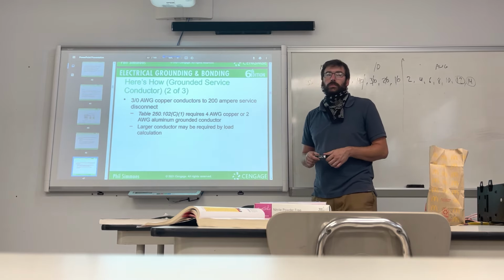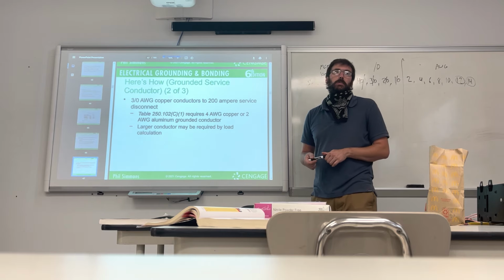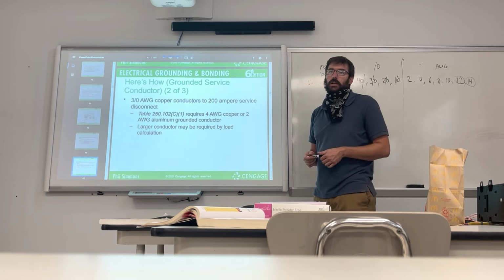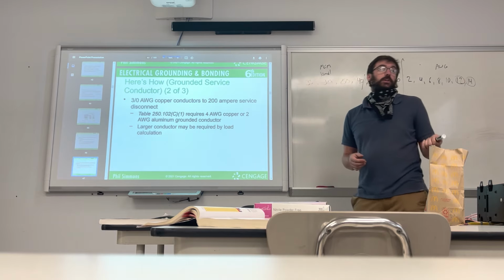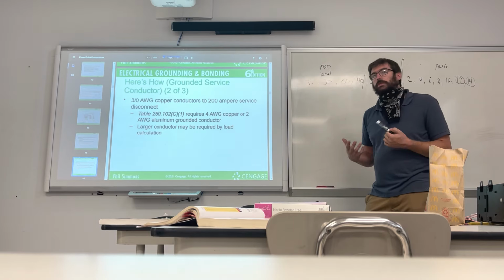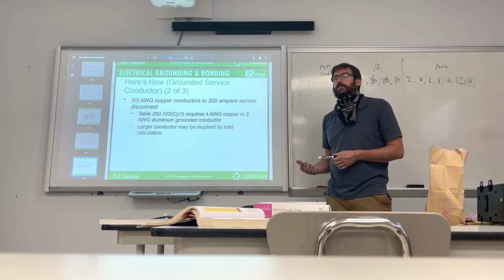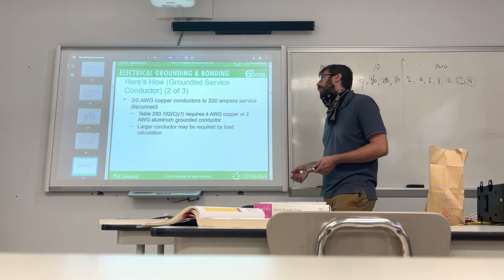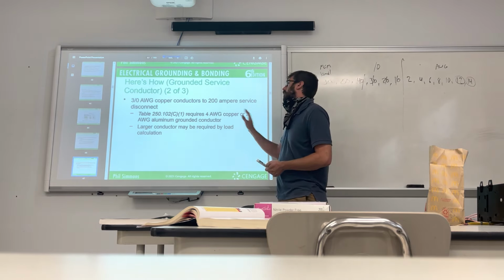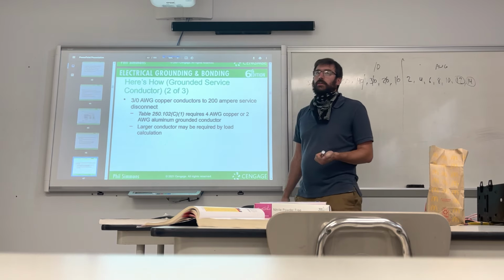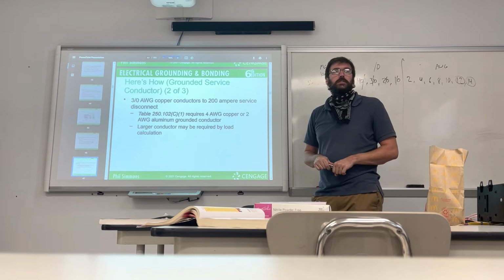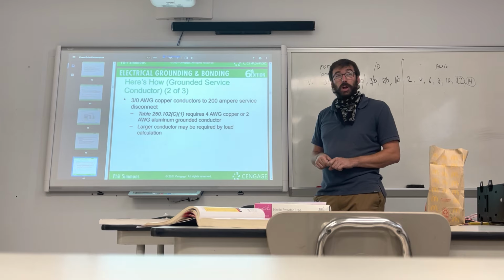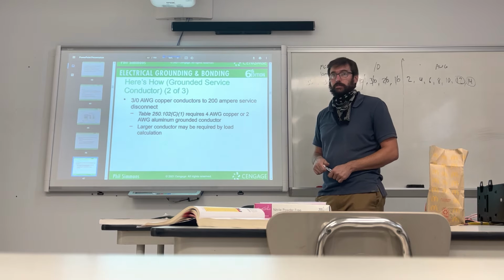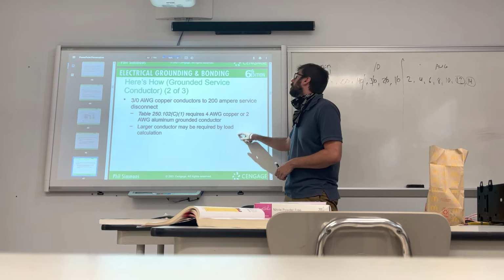Copper. What can handle dirt better? A naked copper wire or a naked aluminum wire? Copper, once again. Copper will oxidize, it's gonna turn green, but aluminum will literally disintegrate if you leave it out in the elements. So that's why most places, like this said, the code allows it, but I have never in all my days seen an aluminum grounding conductor heading out to a ground rod. Never seen it, not once.